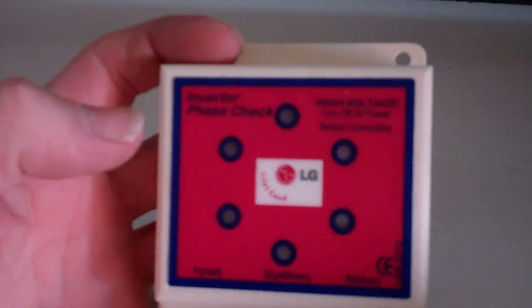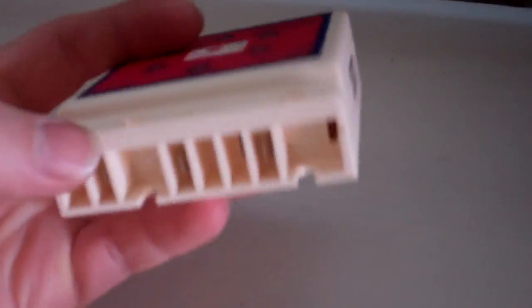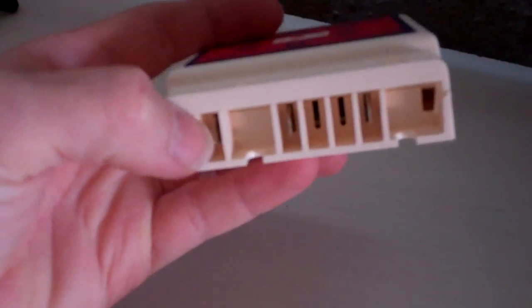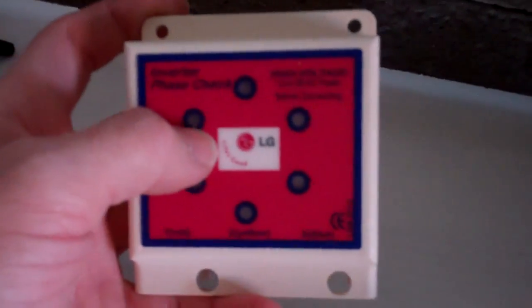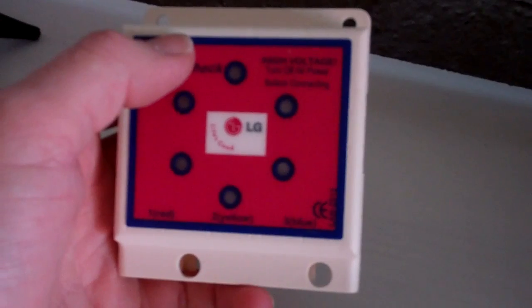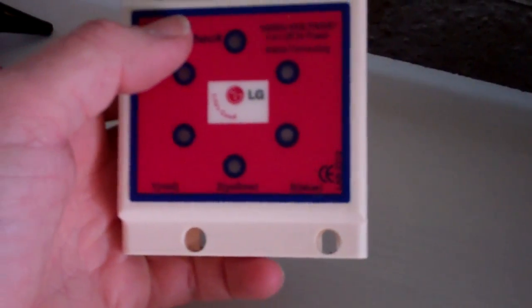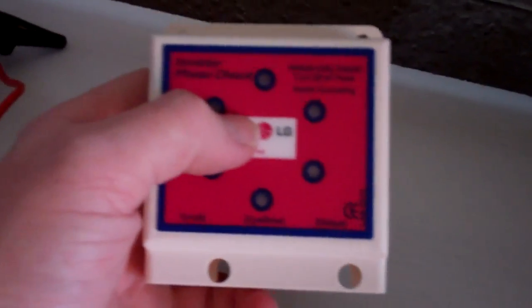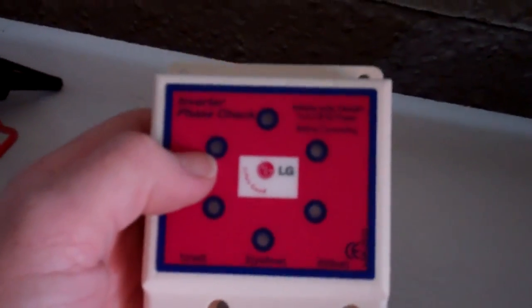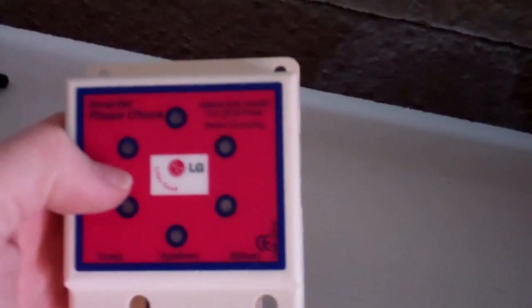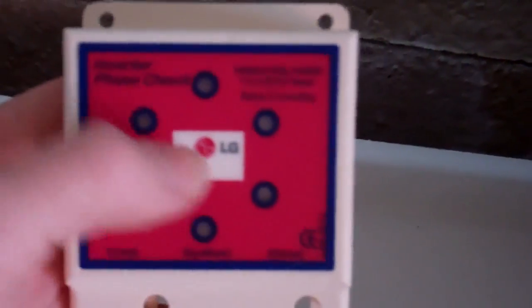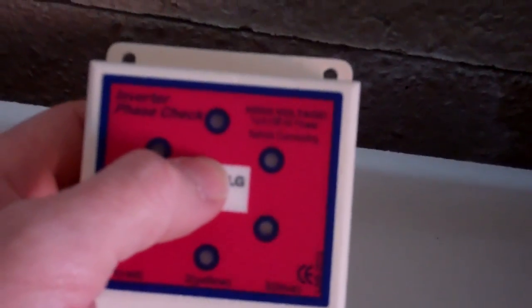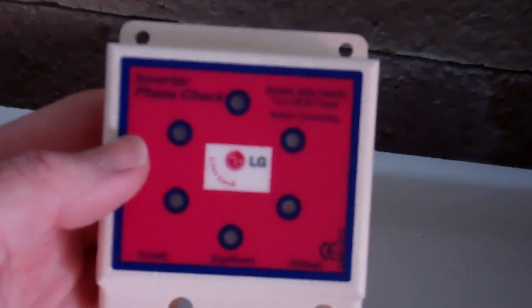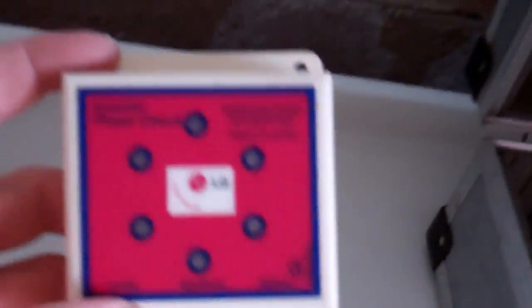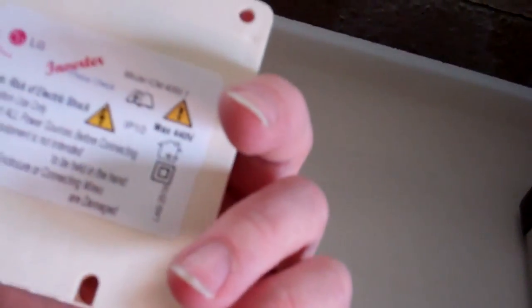It's an inverter checker for mini splits. You put the 3 connections to your compressor on them, 3 pins, and these little LEDs should light up in a sequence. I think they light up in pairs. That'll tell you if all the diodes or whatever in the inverter circuit are powering up the compressor properly. On the LG one, when you go on the LG course, it does 5 little bursts of trying to start the compressor, and if it doesn't start, it locks out. But I'm sure there's videos of these things working. I'll have to get one working one day so you can see what it does. It's a simple little thing.